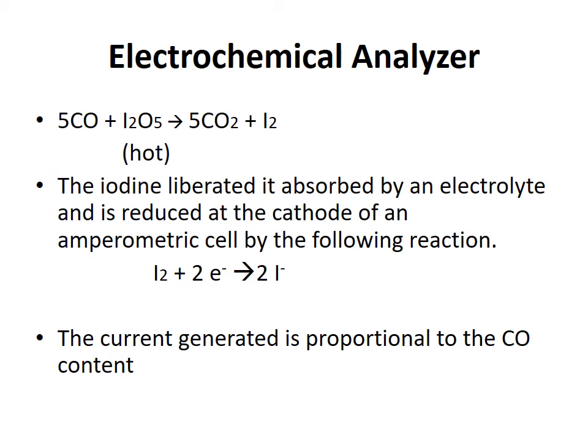The next method for carbon monoxide analysis is the electrochemical analyzer. The gas sample containing CO is passed over hot iodine pentoxide at 150°C, liberating iodine gas: 5CO + I₂O₅ → 5CO₂ + I₂. The liberated iodine is absorbed by an electrolyte and reduced at the cathode of an amperometric cell by: I₂ + 2e⁻ → 2I⁻. The current produced is a quantitative measure of the carbon monoxide content of the sample.